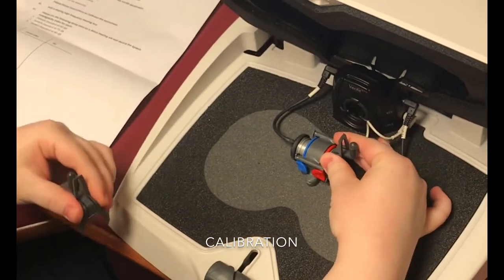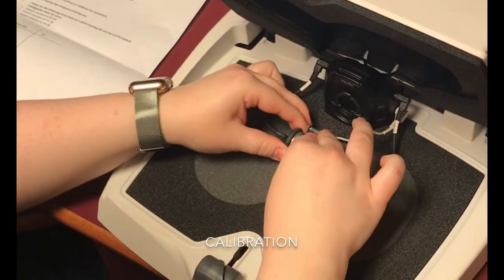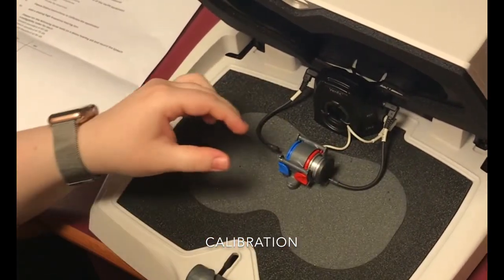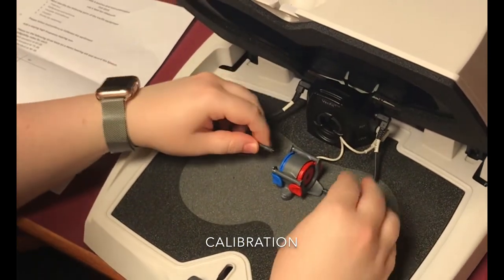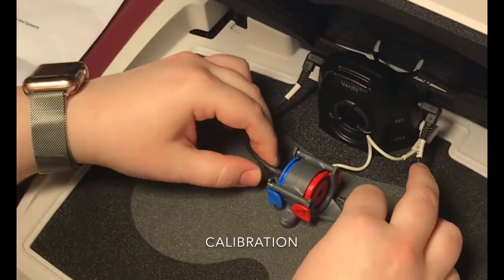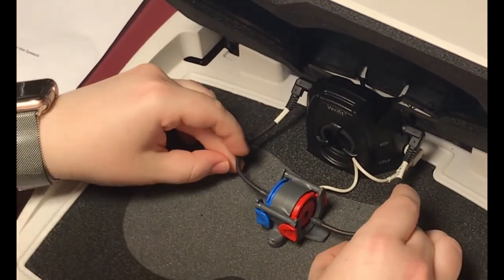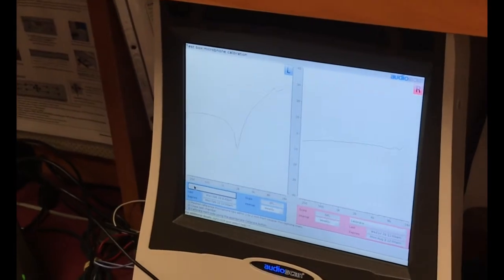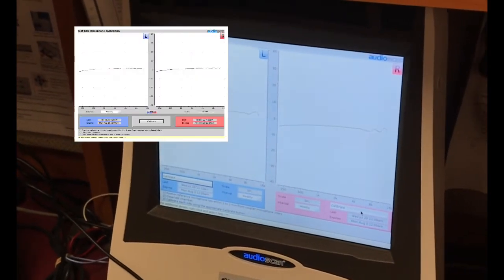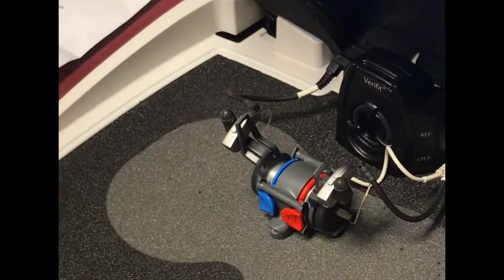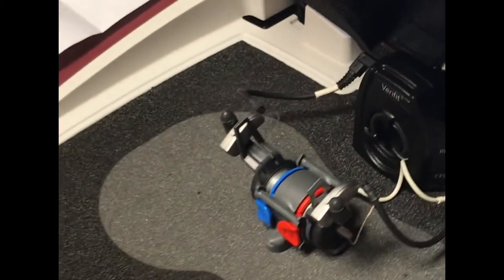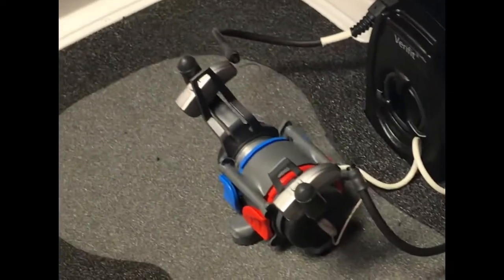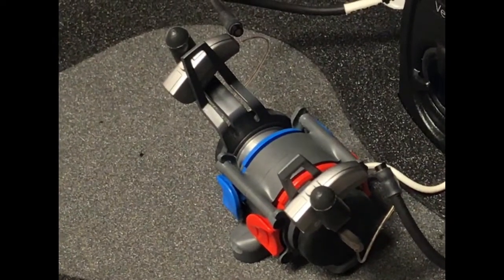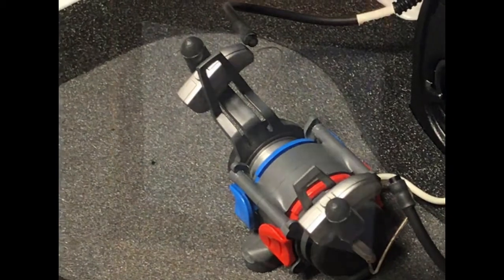Before you start any tests, you want to calibrate. So Esther is taking off the hearing aid clips and the coupler to expose the coupler microphone, and she's positioning the reference microphones very close to the coupler microphone. She's going to run the calibration and look on the left. You will see that the line has flattened out, and that's what we want for calibration, 2 flat lines. Once everything looked good for calibration, you are going to begin your test by putting everything back, the clips, the hearing aid, the coupler, and now you can start your test.